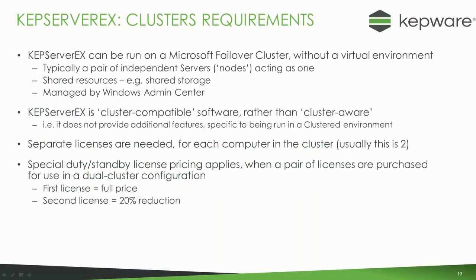In a cluster environment, we see people using Kepware in clusters quite a lot. For those not familiar with clusters, it's a pair of independent servers with shared resources managed by a Windows cluster admin application. There are various grades of software: software made specifically for clusters, software which is cluster aware, and software which is cluster compatible. Cluster aware software has specific hooks in it to be managed in a cluster environment using the Windows admin software. Kepware is not cluster aware — it is cluster compatible, which means it's fine to live in a cluster environment but doesn't have the hooks to be managed by the cluster management suite.